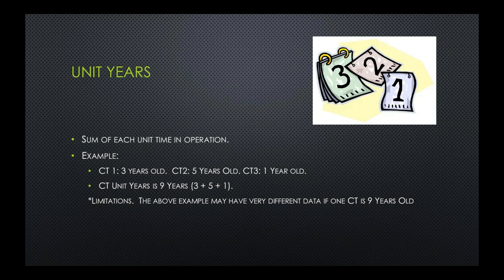This is important because you also have to realize, as the disclaimer at the bottom says, there are limitations to this. If you have 2 CTs, one 10 years old and one 1 year old, that's a lot different than having 2 CTs where one is 6 years old and one is 5 years old, because a 10-year-old CT is going to have a lot more service history and you'd expect quite a few more breakdowns as it moves towards the end of its life.